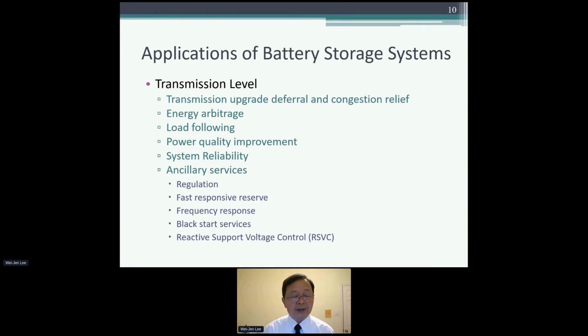The other one is ancillary service, on the power marketing side. You can do regulation - reg up, reg down - and get into so-called fast response reserve. In the ERCOT market and other markets, they have a similar mechanism to involve the battery storage system. They can also help with frequency response, because batteries can do a very fast response, and with current measurement, you can achieve a faster response in the power system.